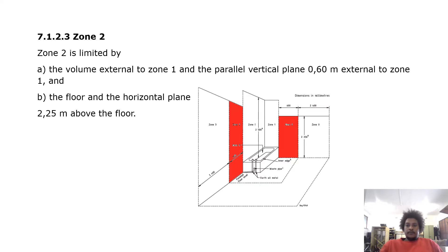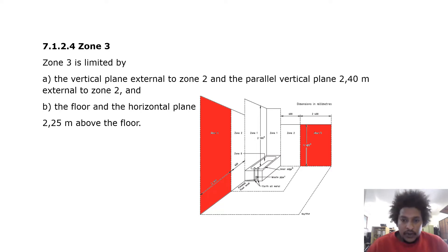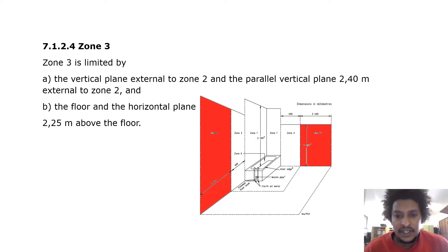Zone 3 is limited by the vertical plane external to zone 2 and the parallel vertical plane 2.4 meters external to zone 2, and the floor and horizontal plane 2.25 meters above the floor. As shown in red in the picture, zone 3 is the same height as zone 2, right next to zone 2 and 2.4 meters on the vertical plane.